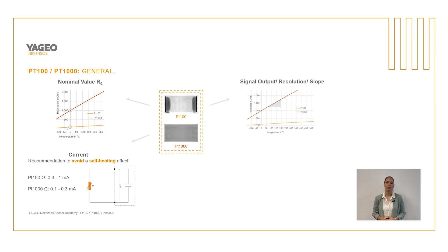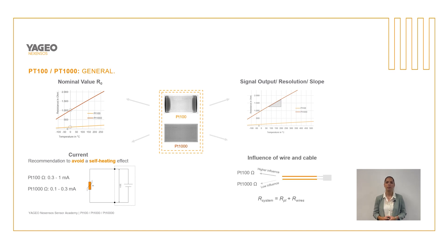The PT1000 also has a steeper characteristic curve, which has a positive effect on the resolution of the measurement signal. Furthermore, the resistance of the connected cable has a greater effect on the PT100, and what this means exactly will be shown on the next slides.